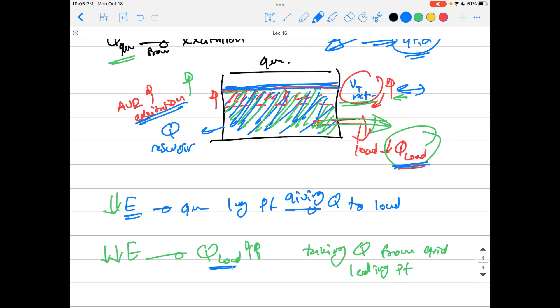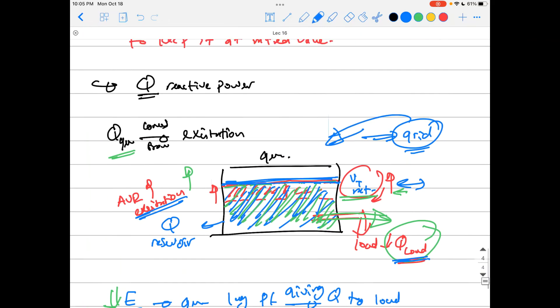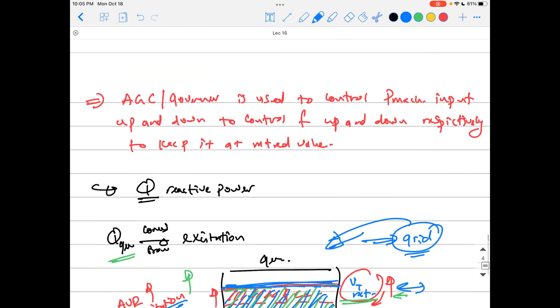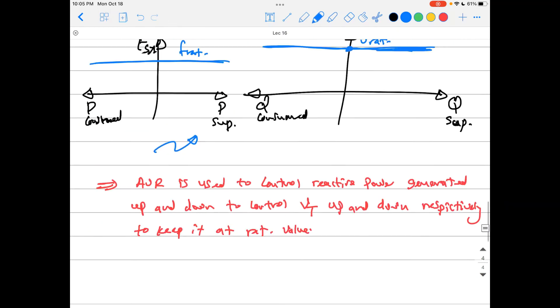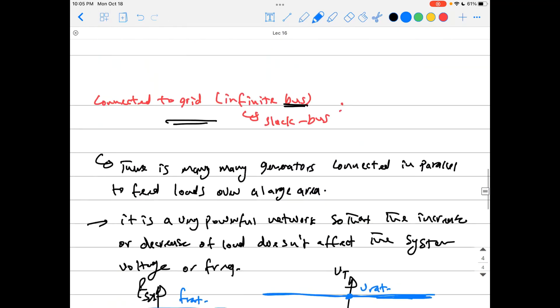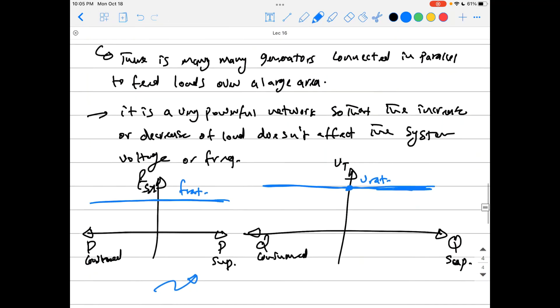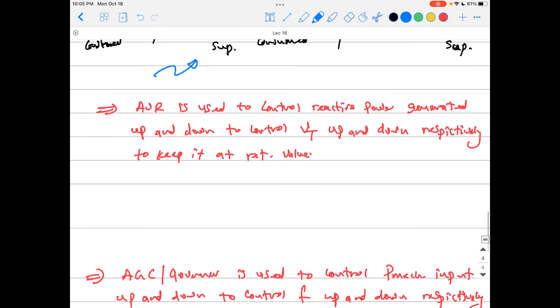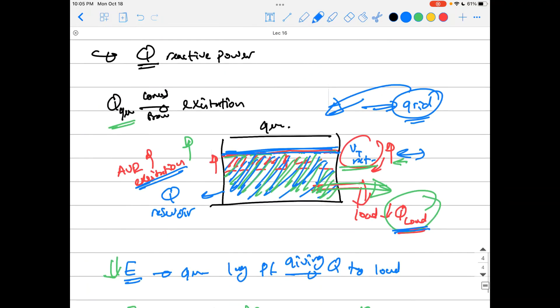Controlling the excitation of a generator while connected to the grid allows you to control the power factor, because you are controlling the amount of reactive power exchange — how much reactive power the machine holds internally or gives to the grid.